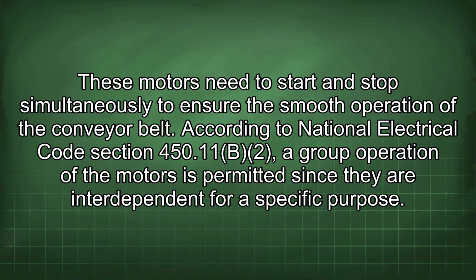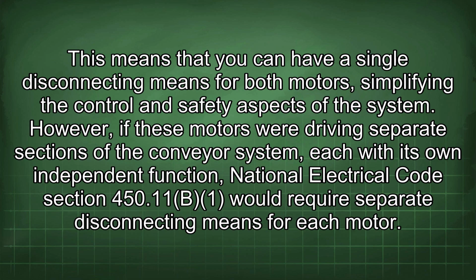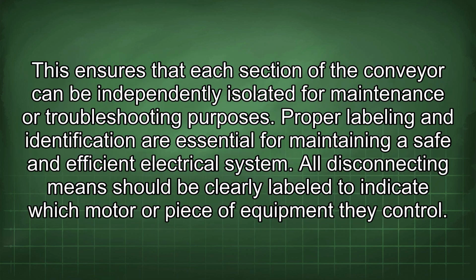According to National Electrical Code Section 450.11(B)(2), a group operation of the motors is permitted since they are interdependent for a specific purpose. This means that you can have a single disconnecting means for both motors, simplifying the control and safety aspects of the system. However, if these motors were driving separate sections of the conveyor system, each with its own independent function, National Electrical Code Section 450.11(B) would require separate disconnecting means for each motor. This ensures that each section of the conveyor can be independently isolated for maintenance or troubleshooting purposes.